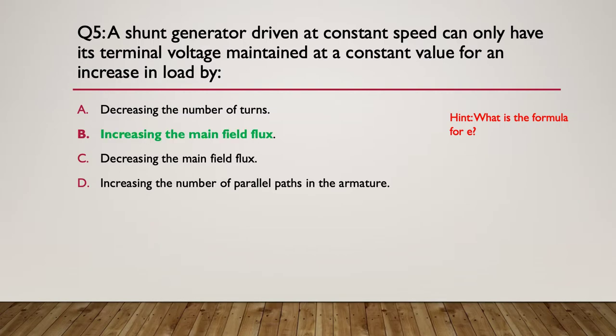The only way you can do it is by increasing the main field flux. You've got to find a way of increasing the field flux as the load goes up, because as the load goes up it wants to pull the terminal voltage down, and the only way to bring the terminal voltage back up is by increasing the main field flux.